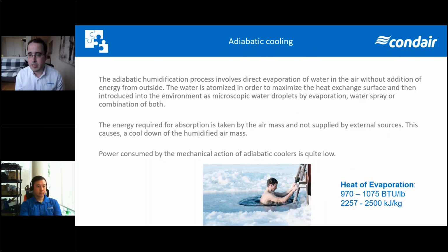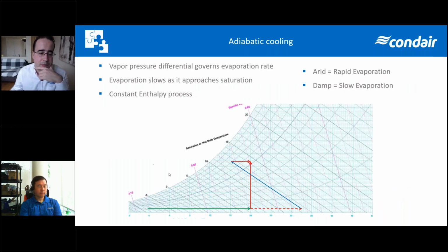Like I said, the difference between adiabatic and isothermal: isothermal is typically steam, so you have to boil the water. It can be gas or electrical, there are different methods, but essentially you boil the water and you get the steam. While with adiabatic, when you spray the water or evaporate the water in the air, the energy comes from the air, so you get your adiabatic cooling. In the psychrometric chart, the red line is a typical steam process. It goes up at the same temperature. While adiabatic cooling, the blue line, goes along constant enthalpy.